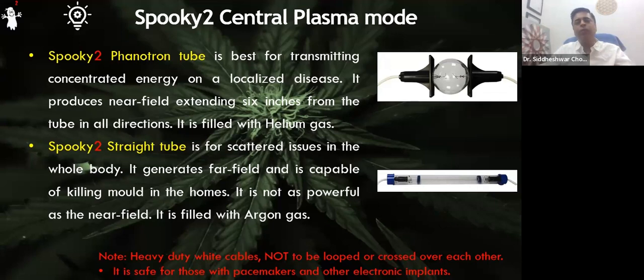You call this field the far field, and the Phanotron tube is called the near field. Now, there's a note here: heavy duty white cables not to be looped. These are the cables connected to the Phanotron tube or the straight tube - very thick cables. Just make sure they are not looped or crossed over each other.